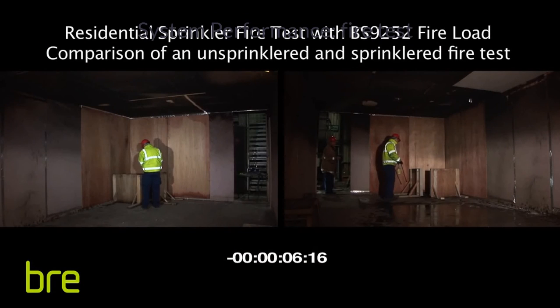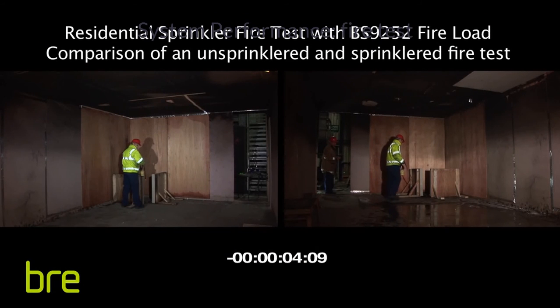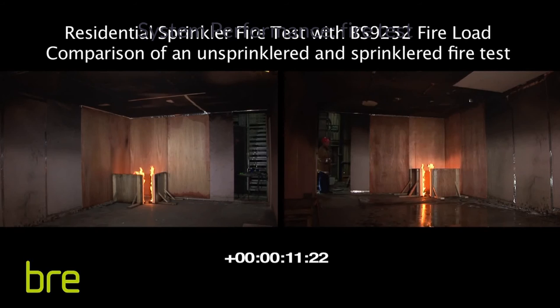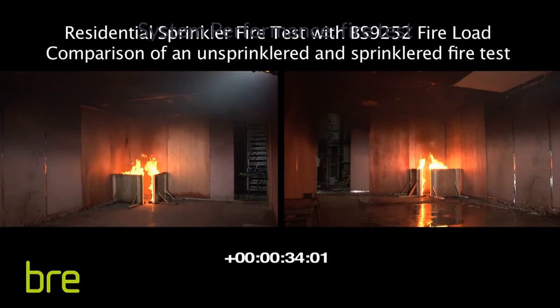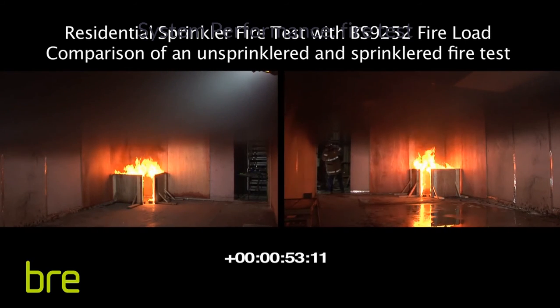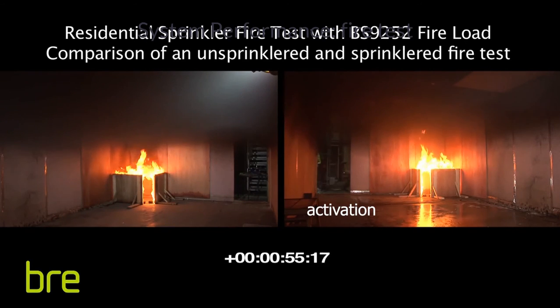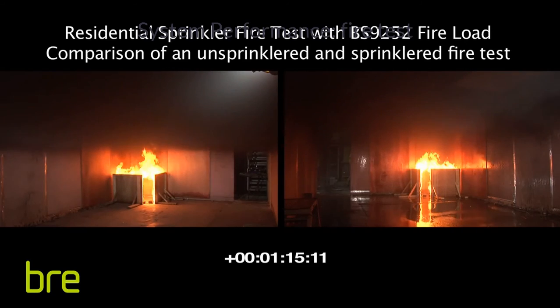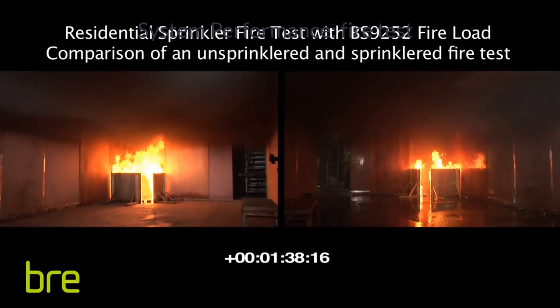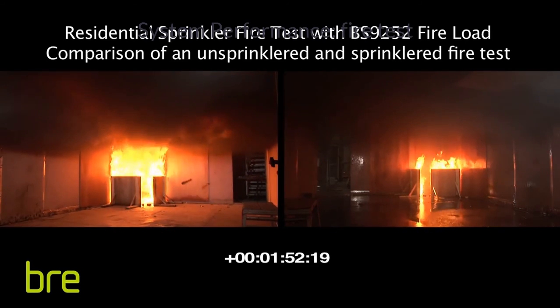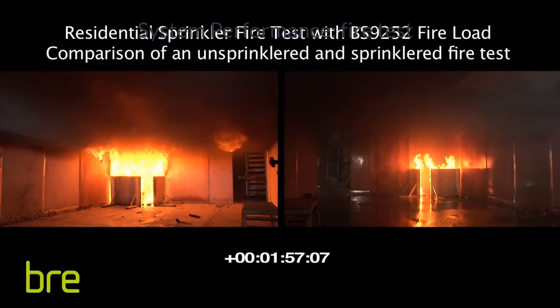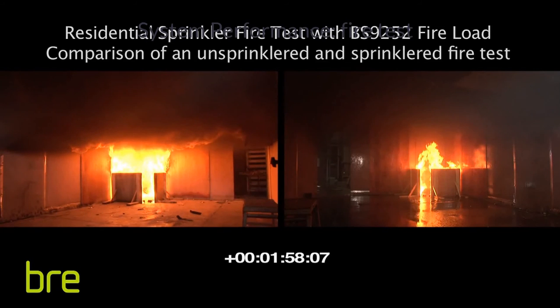So when I talk about the fire test, I'm talking Annex C, I'm talking about this type of setup. It is a stylized furniture test. This just happens to be a sprinkler test where the sprinkler is on the right and the fire burns on the left. And it's a useful video because it shows the purpose of activation, the purpose of suppression, where it is limiting the size of the fire, not letting it progress into dangerous levels, as you can see on the left. So this is what a verifiable performance requirement of a system is, with temperature limits to verify its performance, and which should be verified.